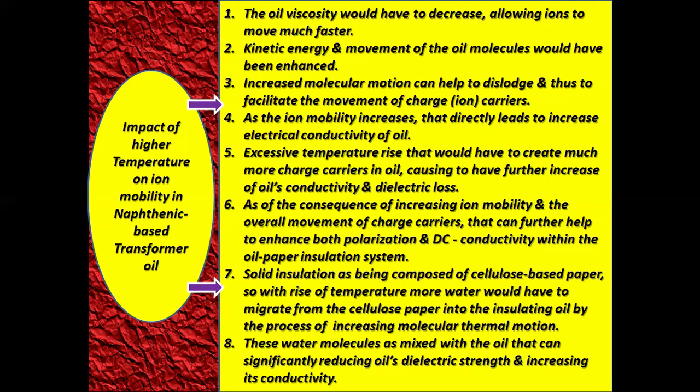As the ion mobility increases, that directly leads to increased electrical conductivity of the oil. Excessive temperature rise creates many more charge carriers in oil, causing a further increase of the oil's conductivity and dielectric loss.